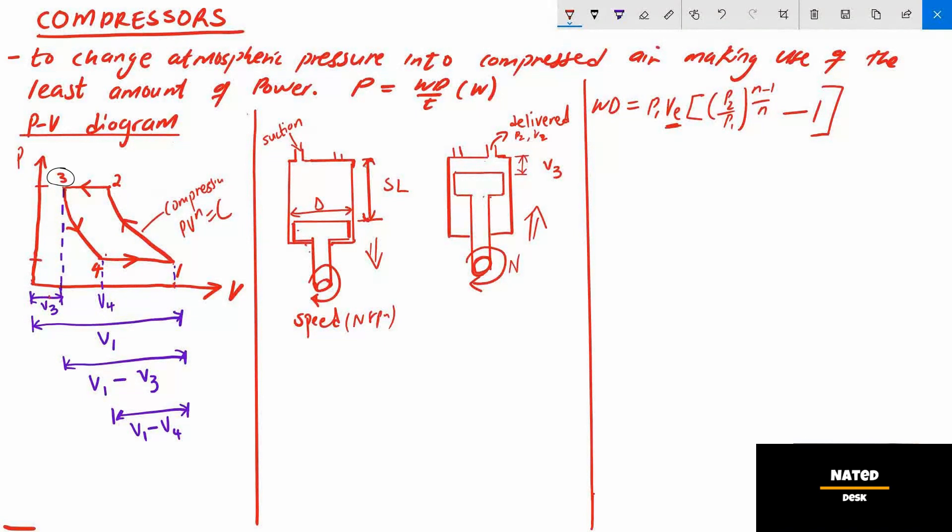V3 is what we refer to as free or clearance volume. This free volume V3 happens when the piston is at the top of its stroke, so it leaves a small space of air between the top of the cylinder head and the piston top. This air is not delivered, it acts as clearance so it remains inside the cylinder.